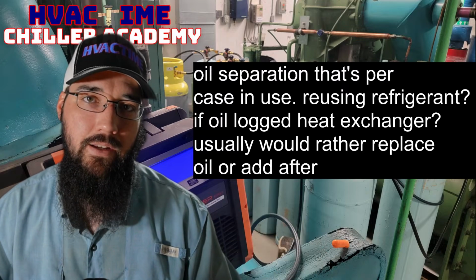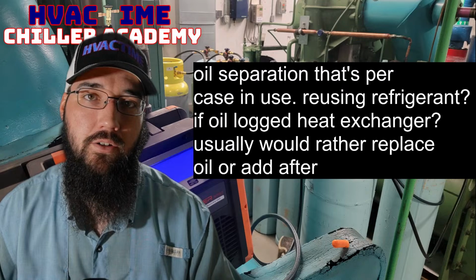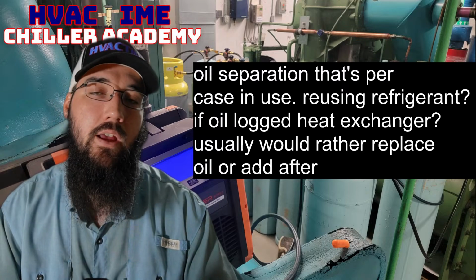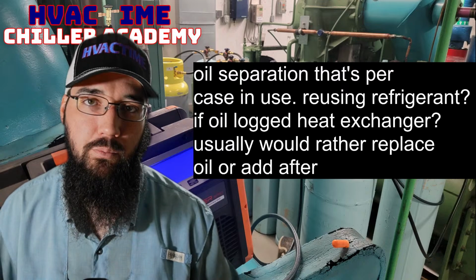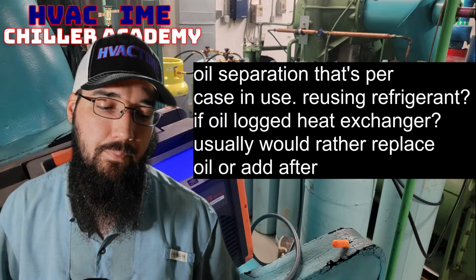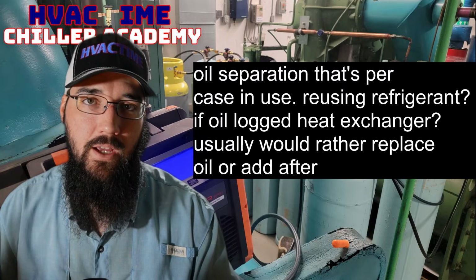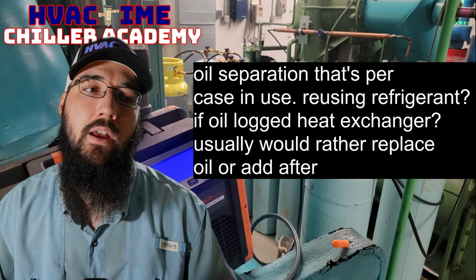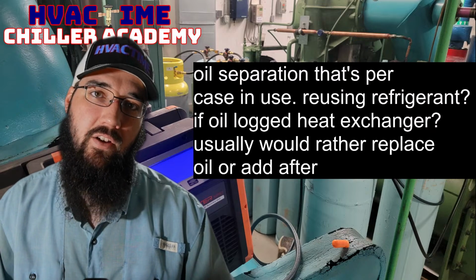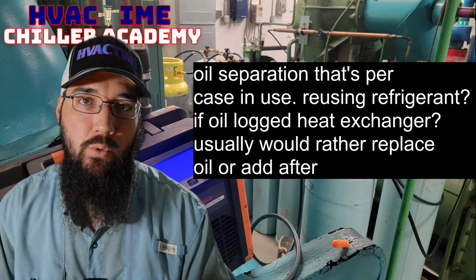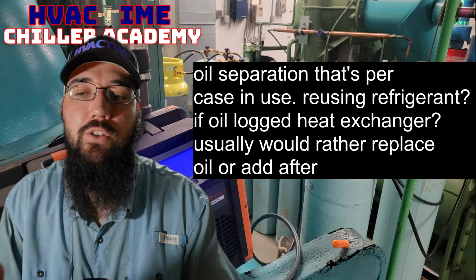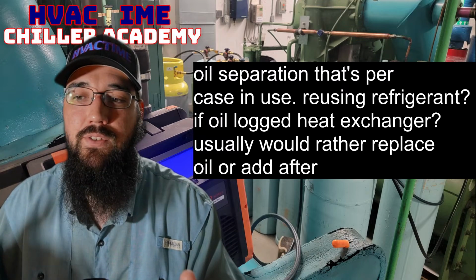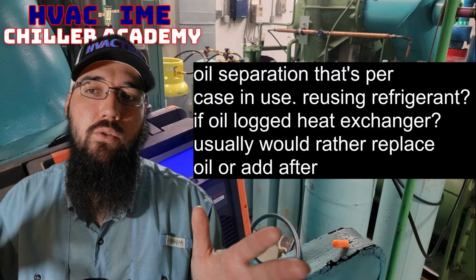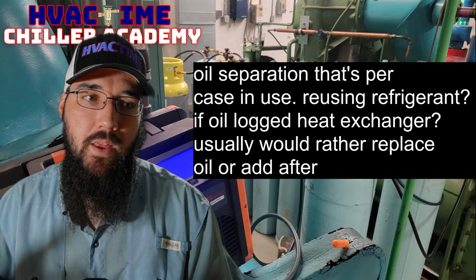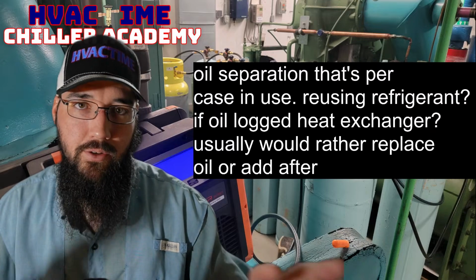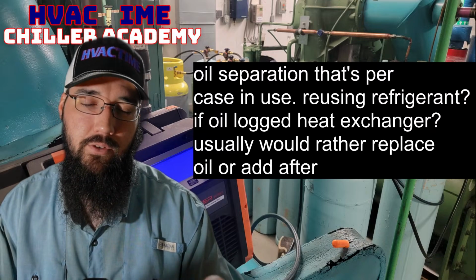And once you get it online, the oil recovery system, whether it's eductors with an RTHD or a gas pump assembly, whatever system they're using to recover that oil back. In a YCIV example, there's no oil recovery mechanism, but those will still stack oil in the evaporator and it can migrate there. At that point, it just needs to run, we need to get that compressor to run. Even if we can get 20, 30 minutes, it may not get everything, but we'll get a pretty good portion depending on the type of recovery they have.